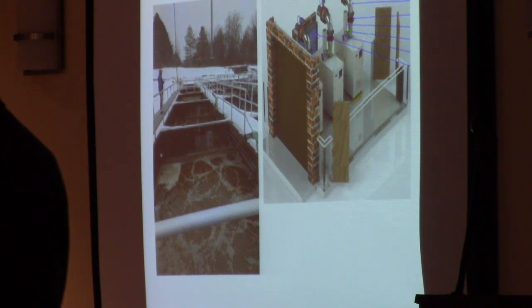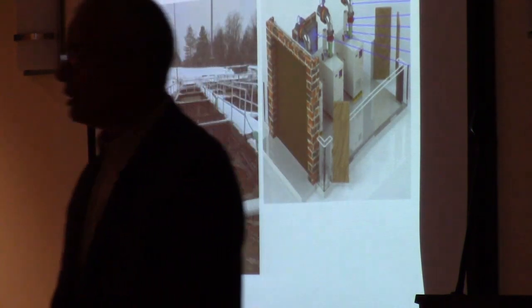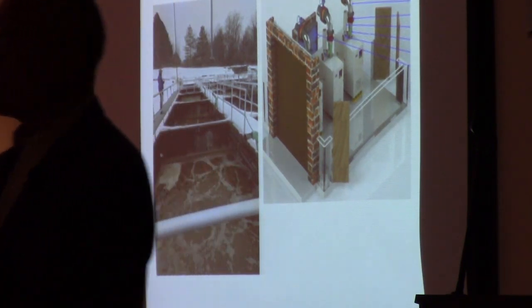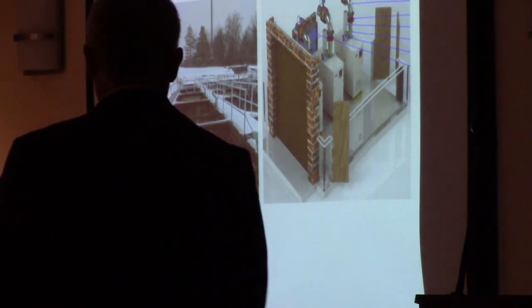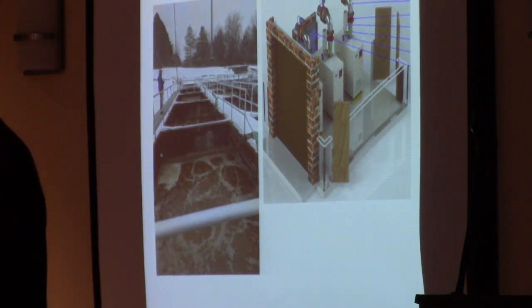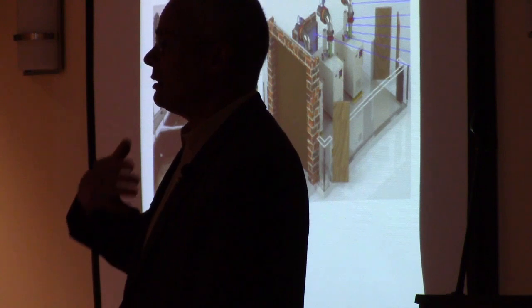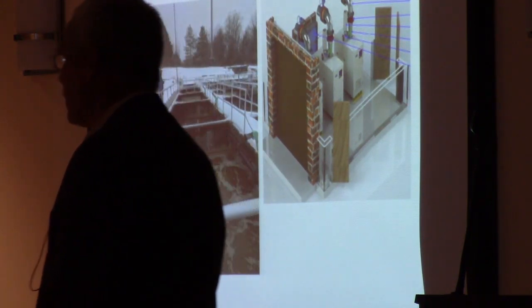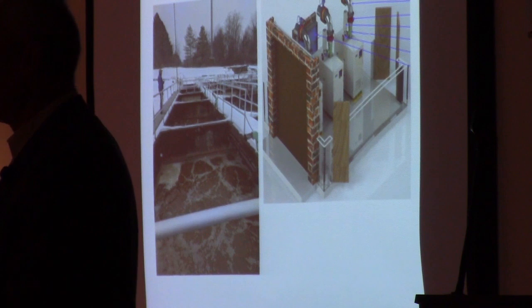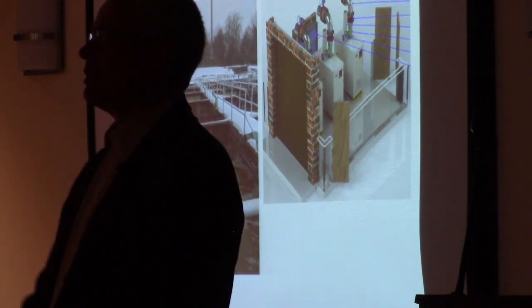The aeration system is where Rick's best workers are. It's millions and millions and millions of bacteria in that tank, and they're the ones doing the work. That aeration tank and all of those microbes need oxygen to survive and to do treatment, and it gets its oxygen from blowers. As Ken mentioned, the blower system providing the air is very old, and the problem is they run constantly. So at 3 in the morning, Rick is doing a bad job because the blower's running, and it really doesn't have to run that fast, but there's no controls to handle that. And then during the day, it might not be running high enough when the load comes in from the facilities.